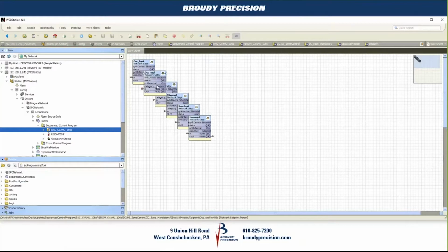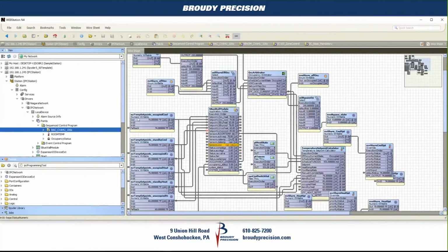As you can see, they each have that nub back to the fallback slot of each of those set points going into the ZO. I hadn't done any programming. I just did a migration, dumped them in here, let the controller run, and I have the CVAHU application up and running without really knowing much or anything about a CIPer 30.